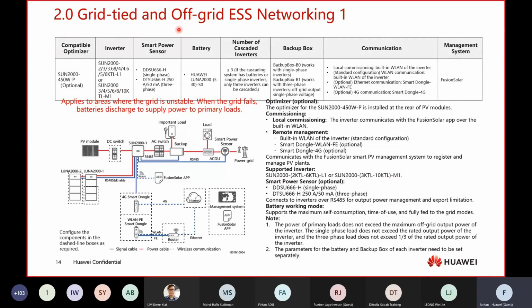So for the off-grid, you need to use the backup box. When you want this solution, you can ask to mention what solution is being used. So for off-grid and grid-tied, this system requires the backup box to be installed. Without this backup box, for off-grid, when the grid is lost, your essential load cannot get the power supply.